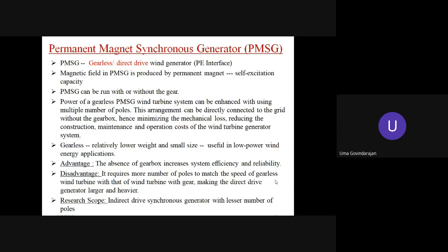So advantages: the absence of a gearbox increases the system efficiency and reliability. And the disadvantages: it requires more poles to match the speed of the gearless wind turbine with that of the wind turbine with the gear, making the direct drive generator larger and heavier. That's all. The research scope is an indirect drive synchronous generator with a lesser number of poles, which one can try. Parallel research is also going on with different rotor configurations and with different permanent magnets. That analysis is also going on in parallel.